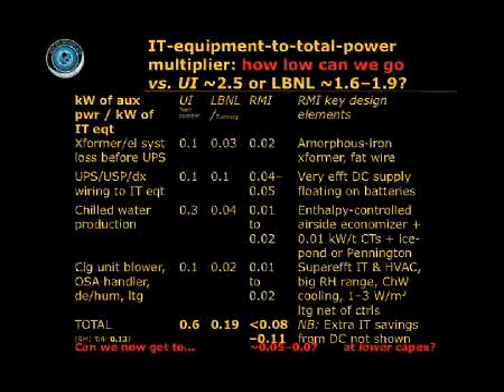Now, for all the air handling and humidity control and lighting, you can use super efficient equipment and mechanicals, an extended RH range, chilled water cooling, and very efficient lights with good controls. In fact, you don't need any lights when there's nobody in the building. The servers don't need light. And actually, maybe we can now envisage getting even below this, down to a 5 to 7% overhead. That's where our latest designs are driving to. Watch this space. I don't think we'll get it lower than 0, but we can get close.